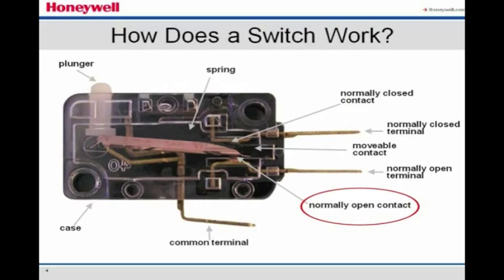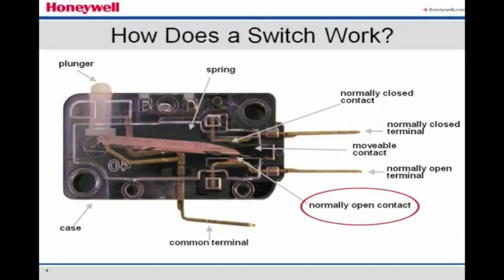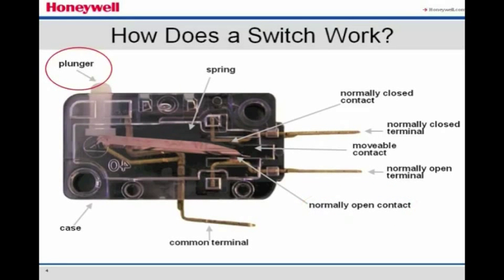Because the mechanism is designed for a snap action, the common contact cannot stop part of the way between the normally closed and normally open contacts. The normally closed circuit is now open, and the normally open circuit is closed. As the plunger is depressed past the operating point, the normally open circuit remains closed, and the normally closed circuit remains open.